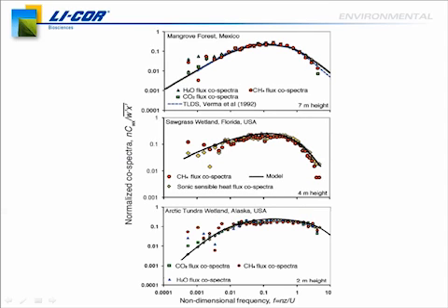That's an important question, and one that we like to address head on, because the instrument does perform very well in the field, and it does a great job of catching the high frequency fluctuations that you need to catch to make a good eddy covariance measurement. And to test that, we've collected data and we've plotted instrument co-spectra.